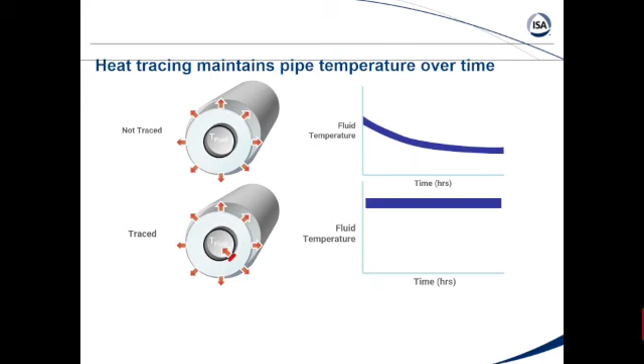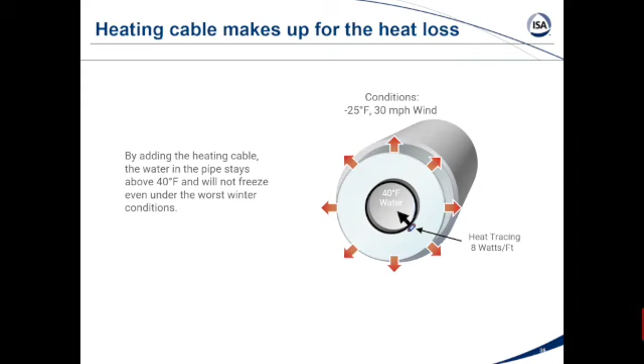And that's what we're up to with most of our stuff, is we basically calculate how much heat is going to be lost through the insulation per linear foot of pipe when we're trying to maintain 40 degrees with certain ambient conditions. And we quantify that, and then we balance that with a little bit of extra heat for safety factor to put back into the pipe. So heat being lost, simply being replaced by the heating cable. And that's mostly what we're up to with heat tracing.